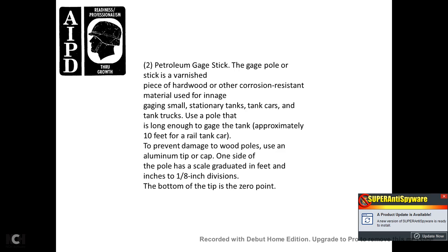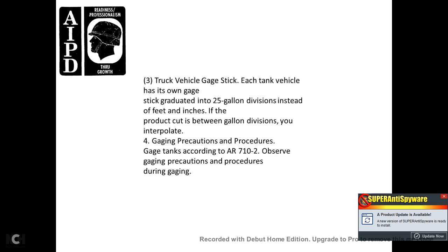15. The petroleum gauge stick, or gauge pole, is a varnished piece of wood or other corrosion-resistant material used for innage gauging small, stationary tanks, tank cars, and tank trucks. Use a pole long enough to gauge the tank — approximately 10 feet for a railway tanker car. To prevent damage to the wood poles, use an aluminum tip cap. One side of the pole is scaled and graduated in inches to one-eighth-of-an-inch divisions. The bottom of the tip is the zero point.